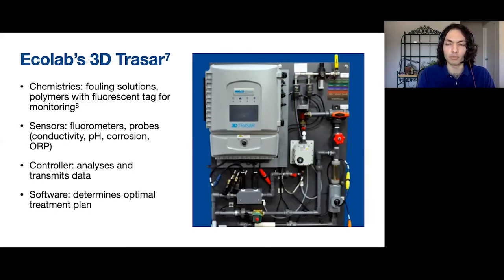The fluorometer in the picture is the white box near the center. This fluorescence correlates directly to the amount of polymer in the system. And the amount of polymer can indicate if there is scaling happening within the system, because if there is, the polymer would be consumed. So imagine this chemistry is going through the system, the fluorometer is reading a constant level of fluorescence, and eventually it starts to go down. That indicates that scaling is happening and it's consuming that polymer, and that's why the fluorescence level goes down.